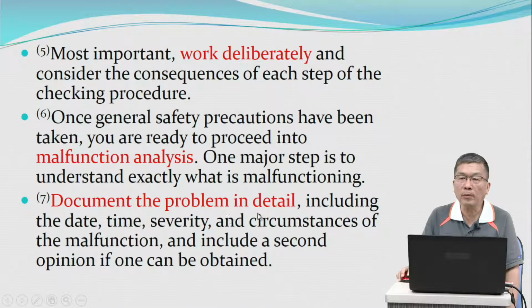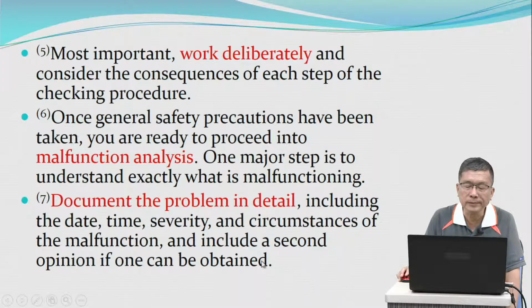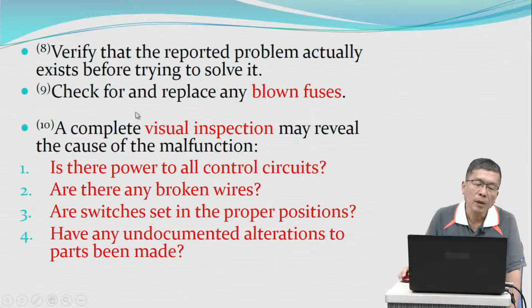Document the problem in detail, including the date, time, severity, and the circumstances of the malfunction, and include a second opinion if one can be obtained. Verify that the reported problem actually exists before trying to solve it.